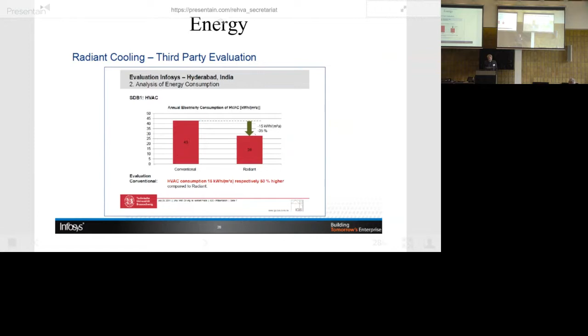Their measurements showed that the building in general was a very low energy building measured in relation to other buildings in India. So it was not like one was very bad and the other side was very good. It was basically the same construction. And the radiant system, the TABS system, still had about 35% better energy performance than the VAV system. Also, when we looked at the comfort, the radiants are here. They are in a more narrow range. The black one is a wider range. And you can even see it was not because the temperatures in the radiant were much higher than in the other part.